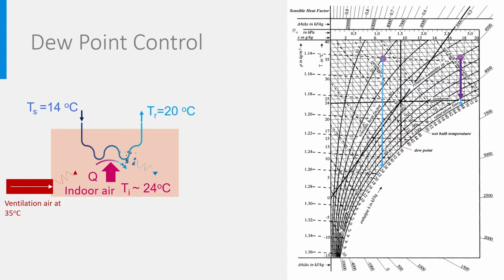In fact, one could say that the real process is not the purple one on the Mollier diagram, but the pink one. Some dehumidification takes place because of the cold water pipe. This is something that must be absolutely avoided, meaning that in such room heat exchangers, the water temperature should be kept above the dew point temperature at any time. You see in the Mollier diagram for the left point with hot air at 20% humidity, that there will be no problems there, as the chilled water with its temperature of 14 degrees is far above the dew point of 8 degrees.